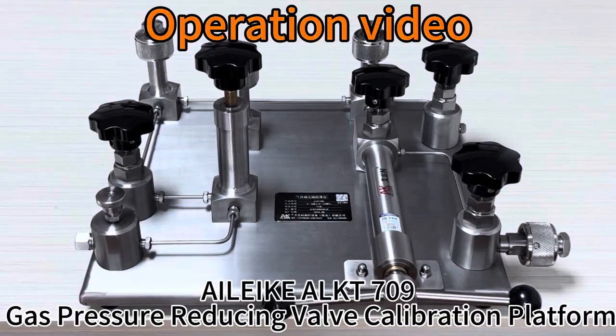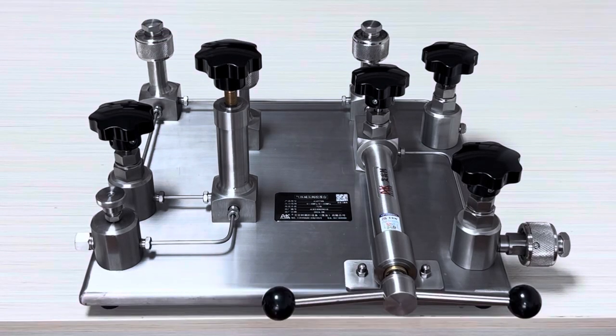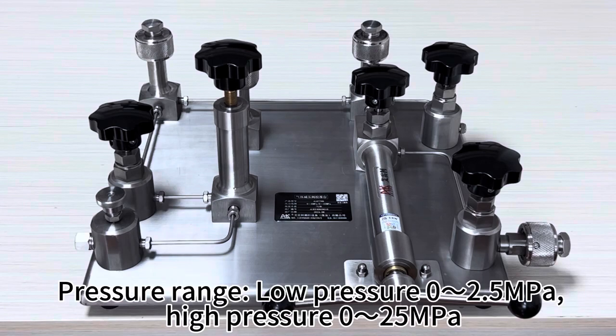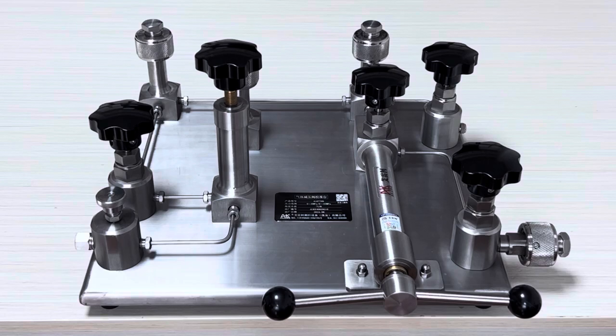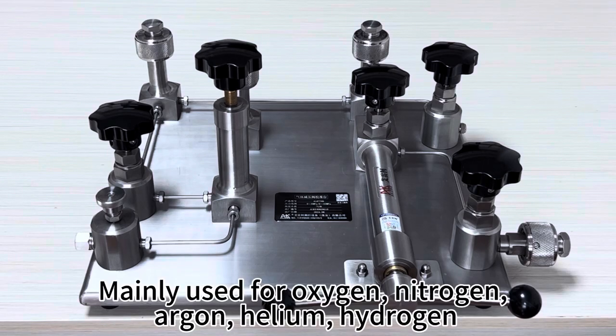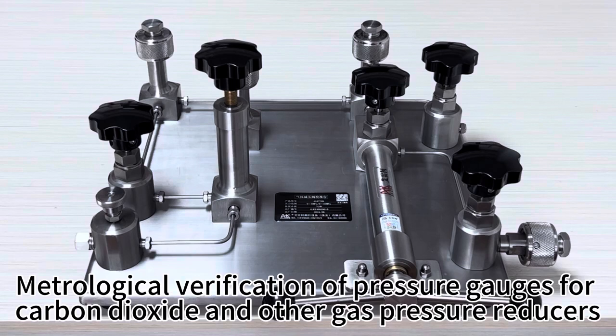AILEIKE ALKT709 Gas Pressure Reducing Valve Calibration Platform. Pressure range: low pressure 0 to 2.5 MPa, high pressure 0 to 25 MPa. Mainly used for oxygen, nitrogen, argon, helium, hydrogen. Metrological verification of pressure gauges for carbon dioxide and other gas pressure reducers.